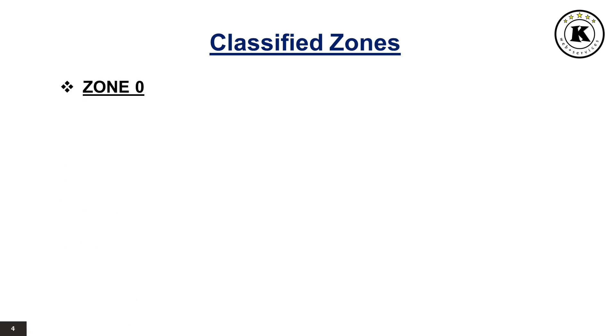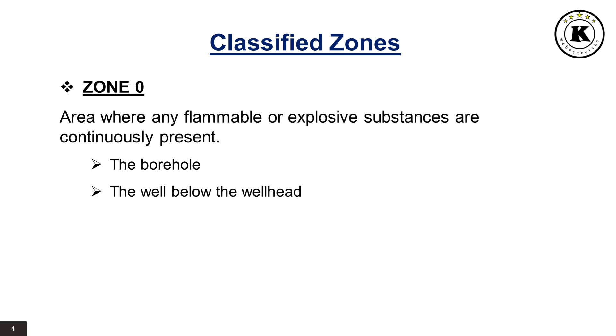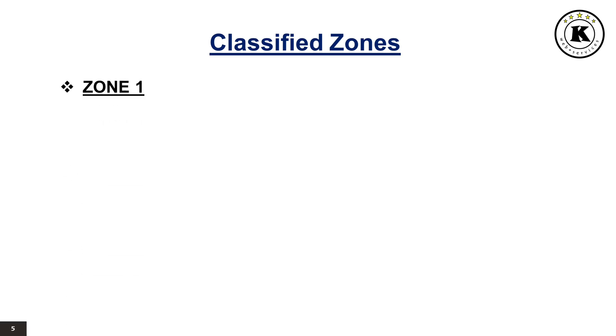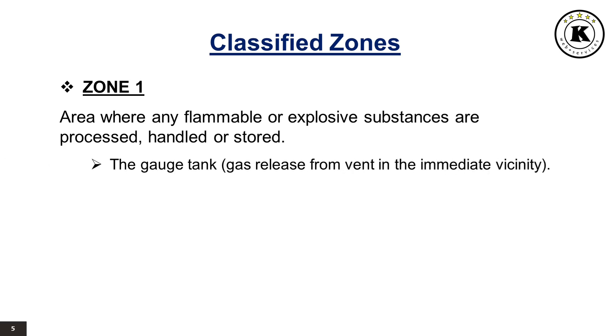Zone 0 is the area where any flammable or explosive substances are continuously present. For example, the borehole and the well below the wellhead. Zone 1 is the area where any flammable or explosive substances are processed, handled, or stored. For example, the gauge tank and gas release from the vent in the immediate vicinity.